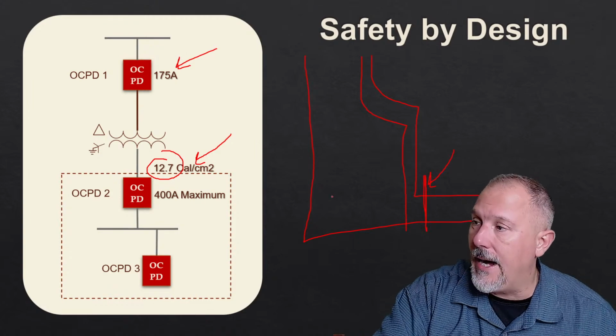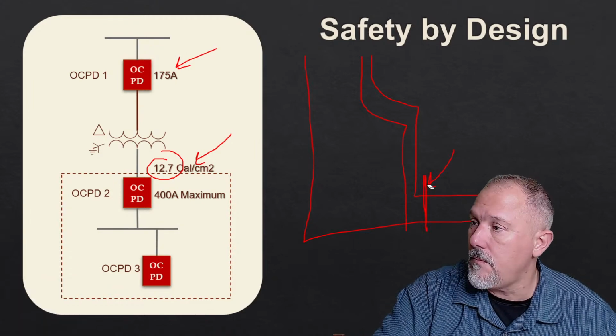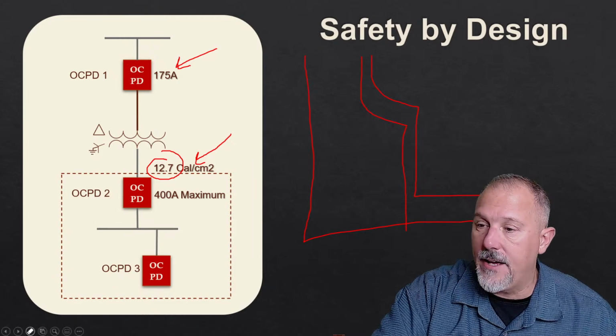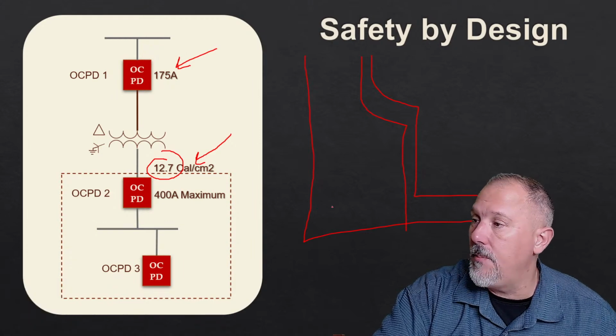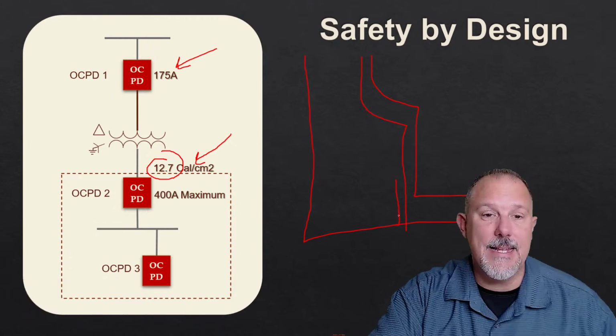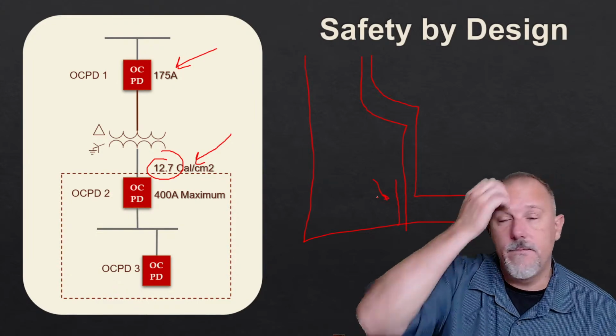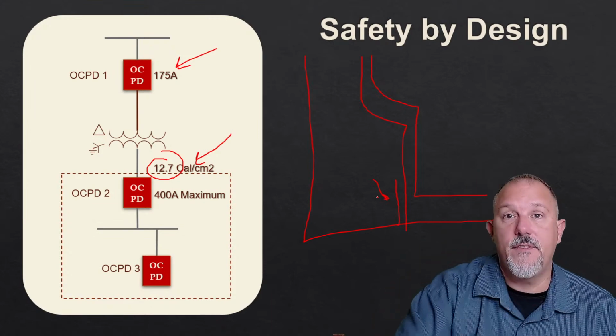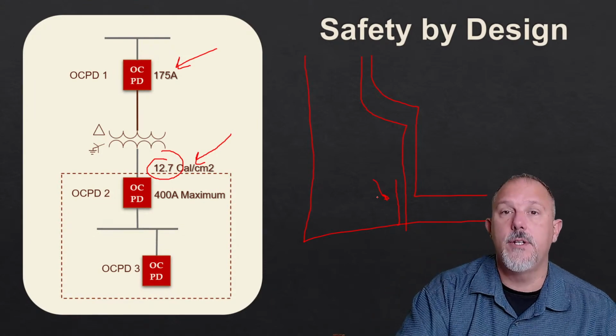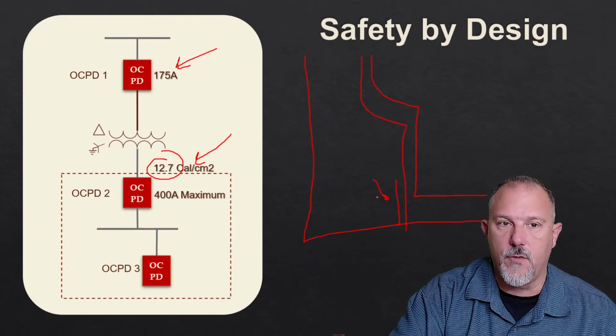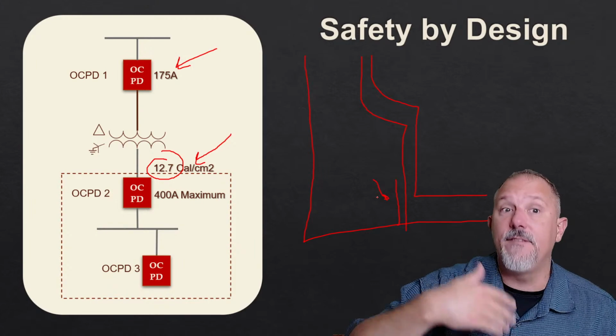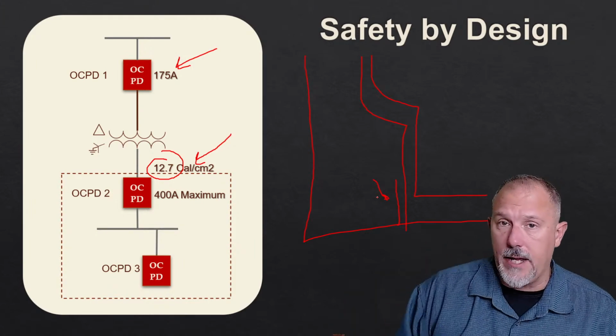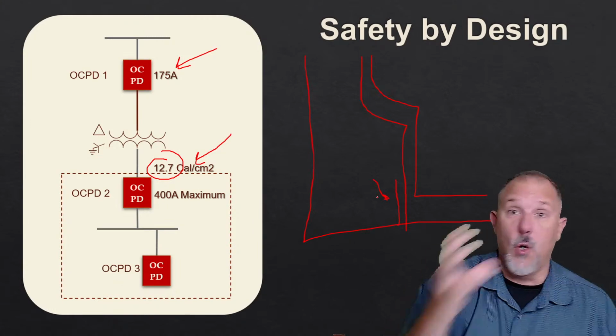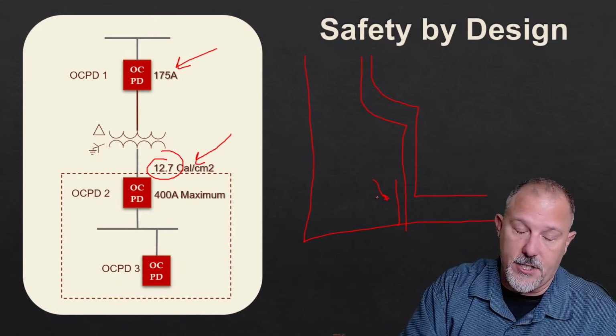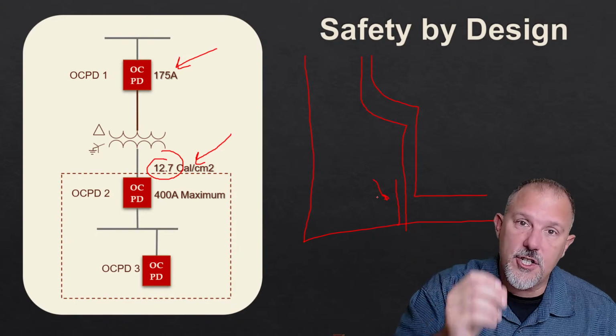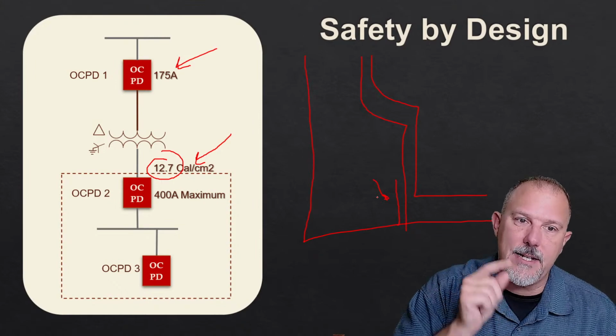So what do I do? I pick a circuit breaker that has an instantaneous pickup where the inrush currents are less than the instantaneous pickup down in that region. That makes life a lot easier for me. So now I don't have to worry about tripping that breaker when I energize a transformer. And there may be other reasons why I go up to 250%. It could be for selective coordination, and that's a whole separate discussion in a different PowerPoint, different presentation. But suffice it to say, I am intentionally adding a delay on the primary of that transformer, so my incident energy will be very high.